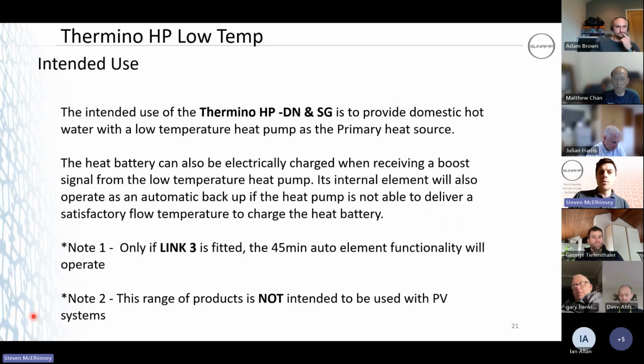So Thermino HP low temp. If you ever get one of these, it'll be a Thermino HP-DN or an SG. So that's a Daikin or a Samsung. Its main purpose is to provide domestic hot water with the low temperature heat pump as a primary heat source. But that heat pump might only be able to achieve a 55-degree flow temperature. So if you think back to the previous module 2, we need a 65-degree flow temperature.